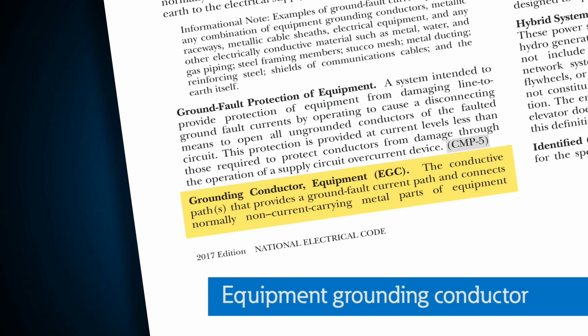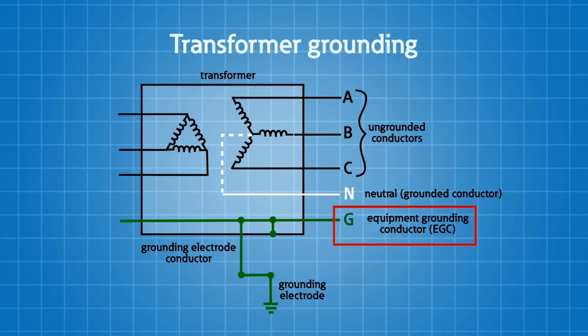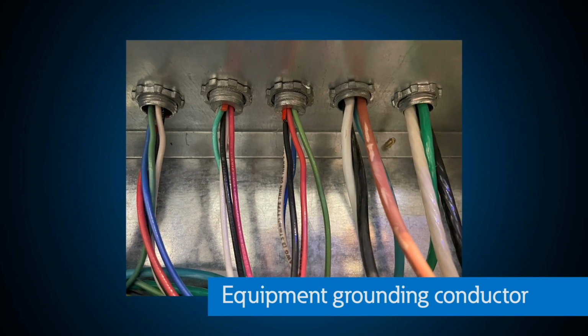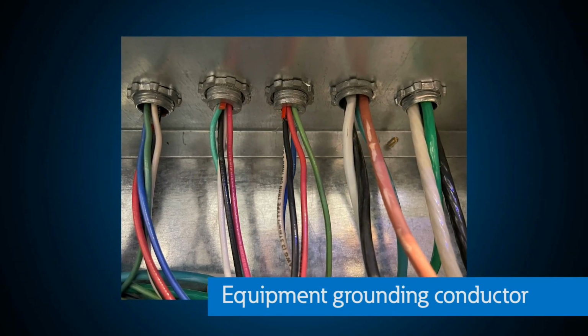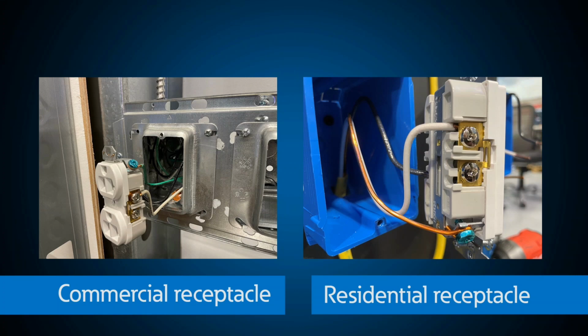Equipment grounding conductor. We've used that term, so let's define it. The equipment grounding conductor is the conductive path that is part of an effective ground fault current path and connects metal parts of the equipment to the system neutral or grounded phase conductor. And that's done back in one location. Think of this as that bare copper conductor that you carry out to all of those loads. Or if you open up any receptacle, you'll see that bare copper conductor in the receptacle outlet. That is your equipment grounding conductor. We want that to be low impedance and we want that to carry fault current should a ground fault occur in the system.